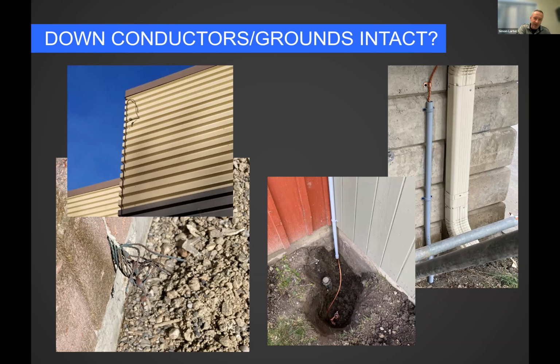I showed you some pictures from that. The down conductors are tin coated class 2 copper poured directly into the concrete columns. The electrician, Western Electrical, did that for us. They ran the conductors up for us in the concrete column pours, poked them out at the top, then we put the through roof connectors on it and bonded it to the steel at the top. But you would never see that because it's poured in. The intermediate loop conductors also poured into the concrete pour.